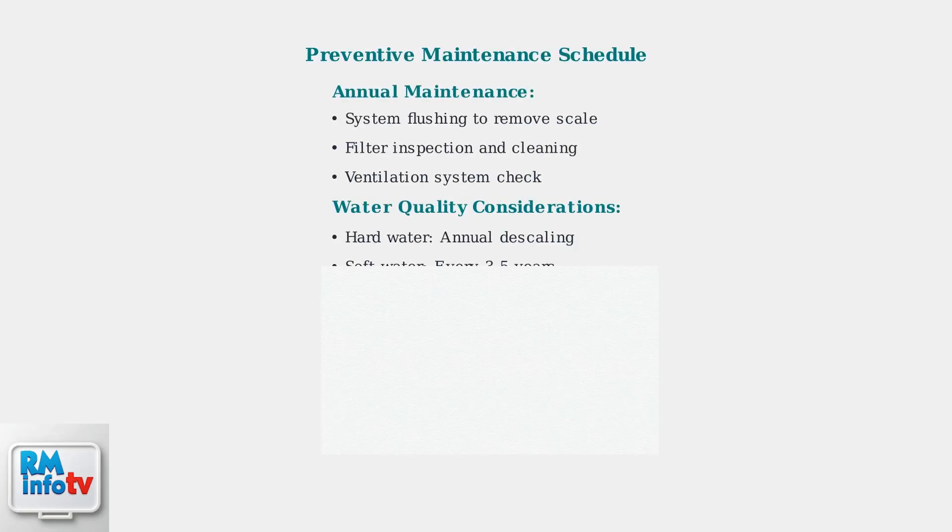Preventive maintenance is crucial for avoiding problems. Flush your system annually to remove scale buildup. In hard water areas, perform this maintenance yearly, while soft water areas can extend this to every three to five years.